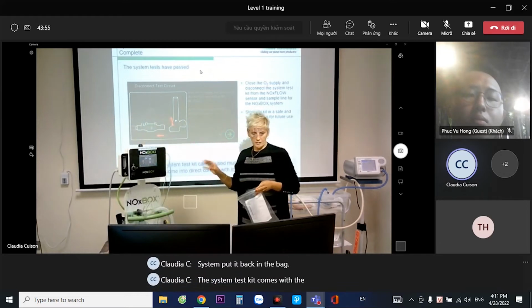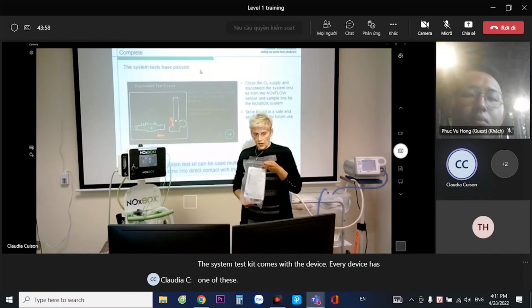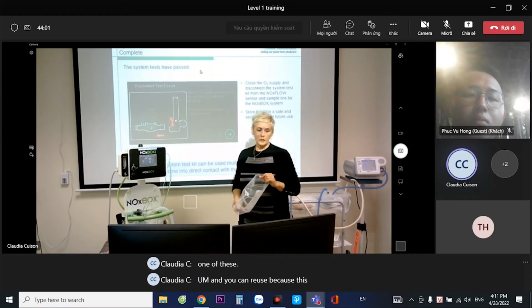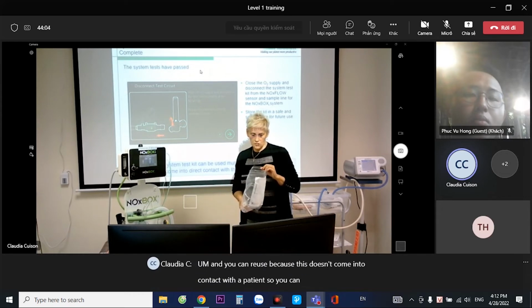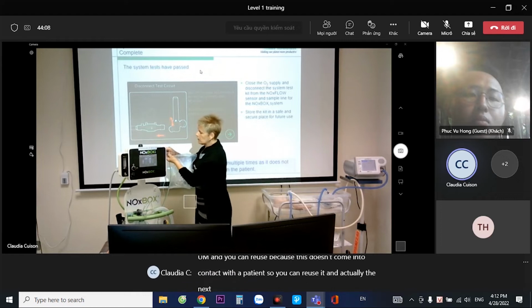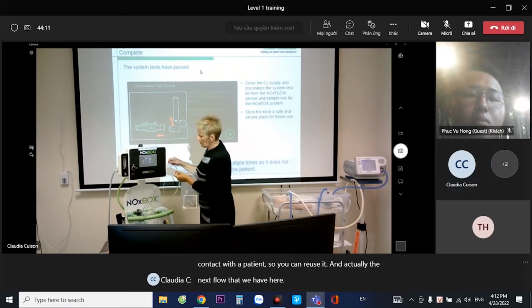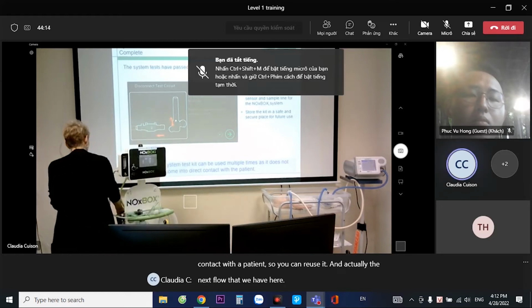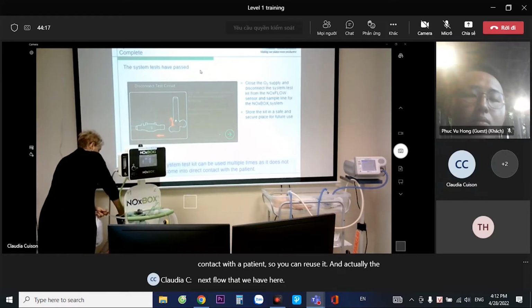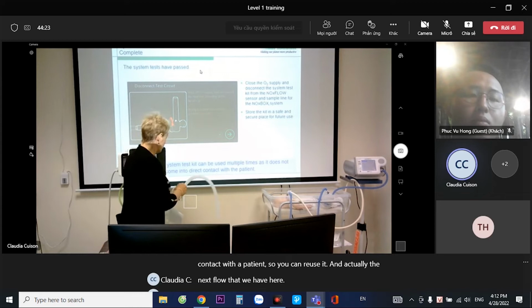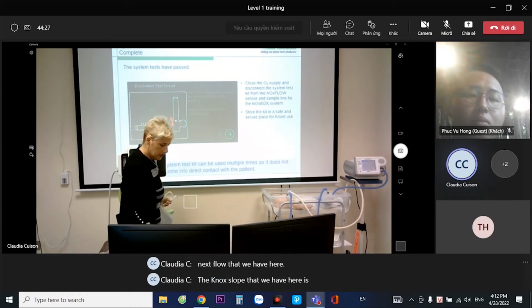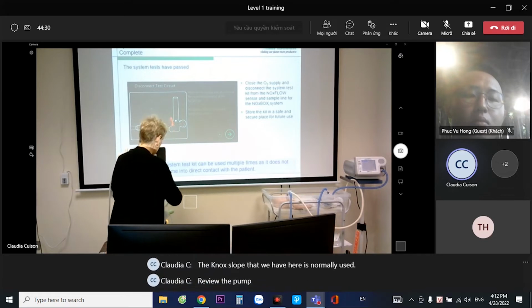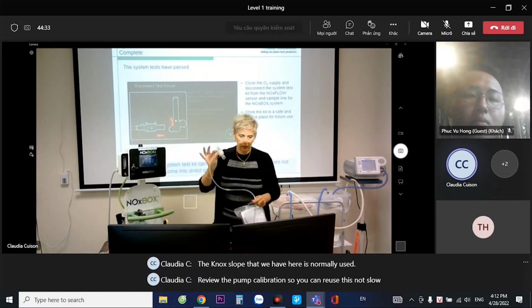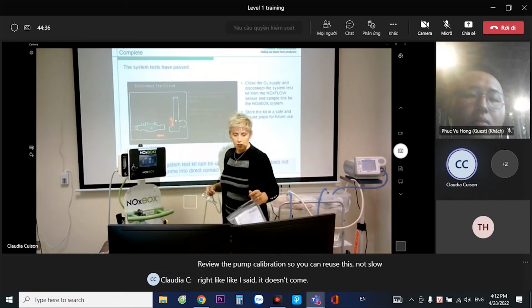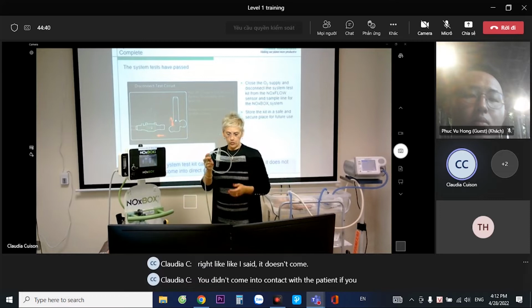The system test kit comes with the device. Every device has one of these. And you can reuse it, because this doesn't come into contact with the patient. And actually, the NOx flow that we have here is normally used to do the pump calibration. So you can reuse this NOx flow, right? Like I said, it didn't come into contact with the patient.